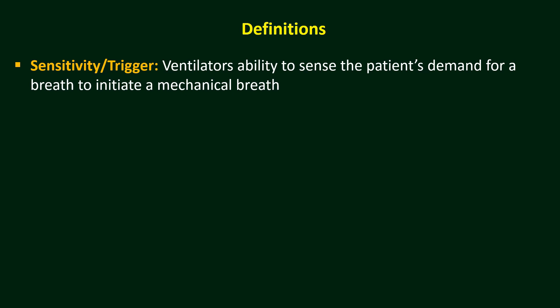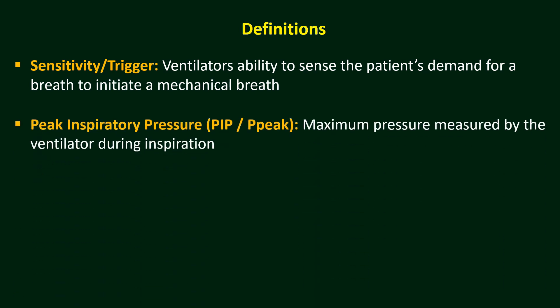Sensitivity or Trigger is the ventilator's ability to understand the patient's demand for a breath in order to initiate a mechanical breath. We shall see more detail in subsequent slides. Peak Inspiratory Pressure, PIP or Ppeak, is the maximum pressure measured by the ventilator during inspiration.